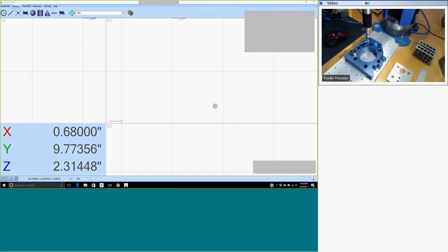Today I'm going to give a brief demonstration on a basic XY line, starting and reporting on the zCAT using Mark IV software. It is a little bit different than the typical coordinate measuring machine in that the machine itself sits in the middle of the part.